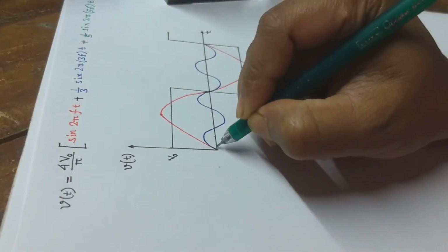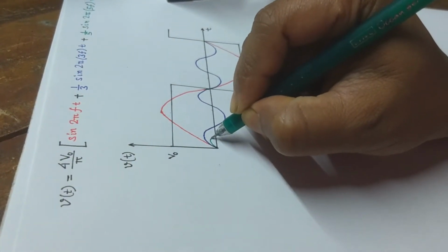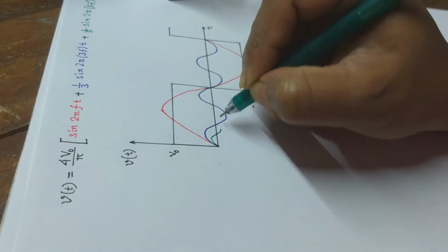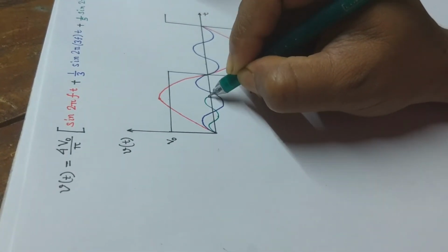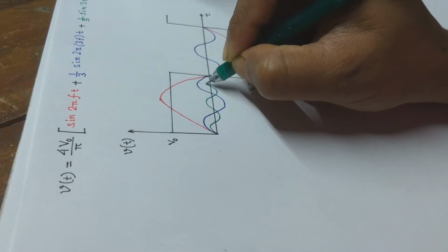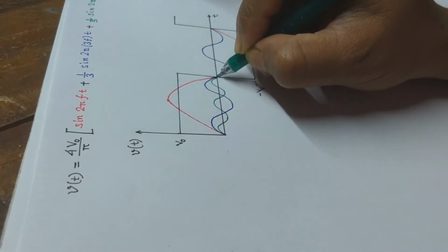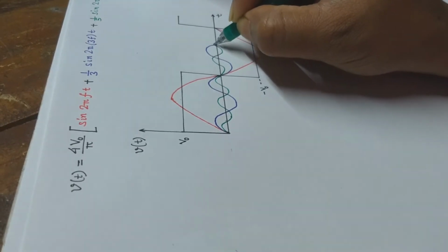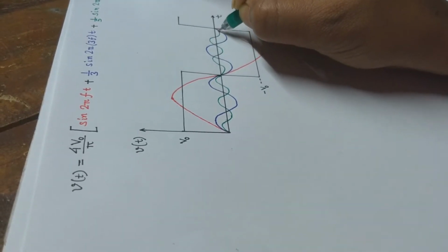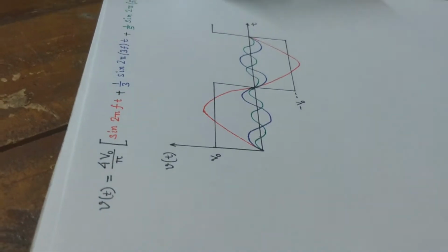There are three kinds of inverters commonly available in market. Square wave inverter, which is the simplest one and unfortunately the worst one, because square wave is packed with a lot of higher frequency harmonics. Most of the electrical equipments we use in our daily days are not designed to handle square wave. Particularly the inductive loads never become happy with that kind of waveform.